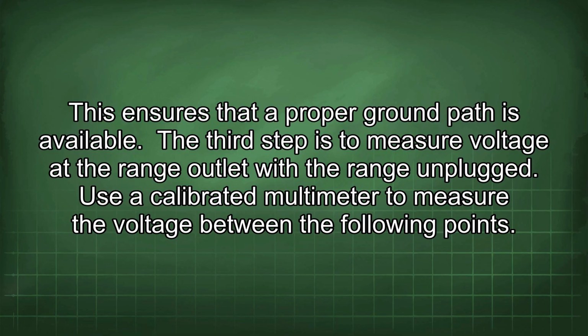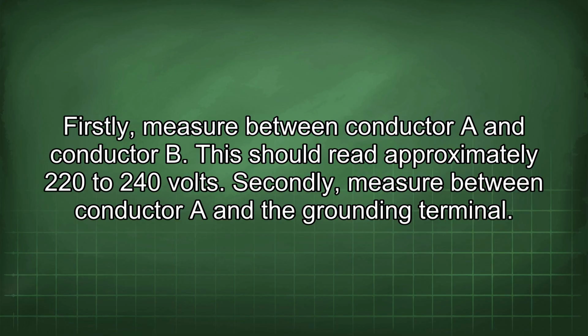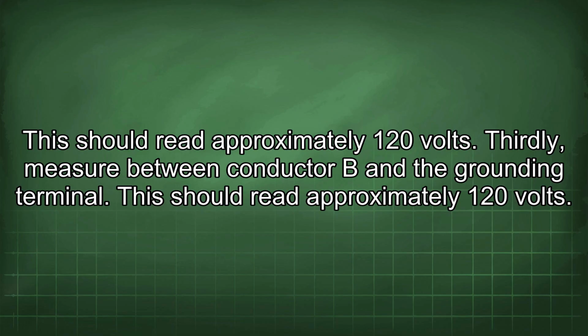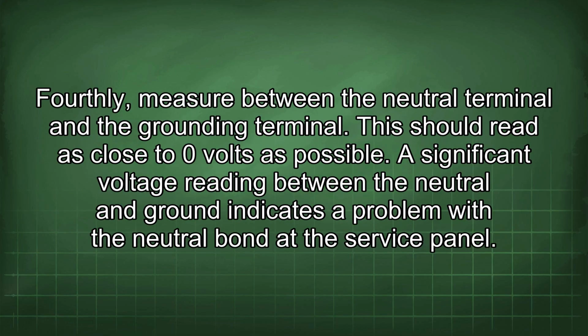The third step is to measure voltage at the range outlet with the range unplugged. Use a calibrated multimeter to measure the voltage between the following points. Firstly, measure between conductor A and conductor B. This should read approximately 220 to 240 volts. Secondly, measure between conductor A and the grounding terminal. This should read approximately 120 volts. Thirdly, measure between conductor B and the grounding terminal. This should read approximately 120 volts. Fourthly, measure between the neutral terminal and the grounding terminal. This should read as close to 0 volts as possible. A significant voltage reading between the neutral and ground indicates a problem with the neutral bond at the service panel.